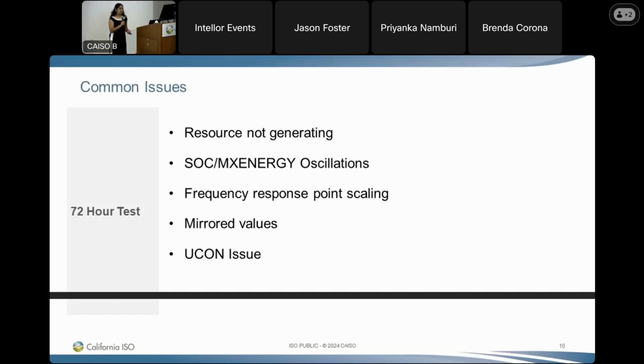Okay, moving on. Now let's talk about some of the common issues we see during a 72-hour test. If the resource is not generating and we don't have enough operational data, we cannot complete the 72-hour test, because as part of the test we ensure some of the logical calculations are also working well. So if we have to check whether a UCON is working well, we need to know whether the logic is working when the resource is generating and when the breaker is closed, and also the scaling and polarity. So to verify a lot of the telemetry information, we need some generation data during that 72-hour period to complete the test.